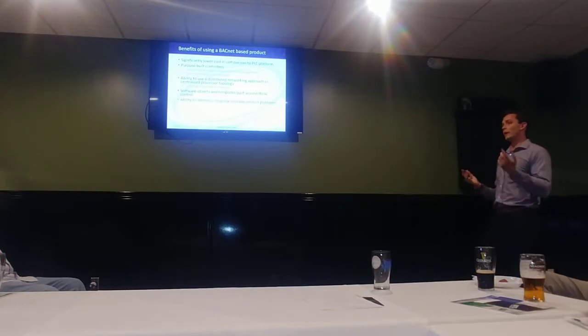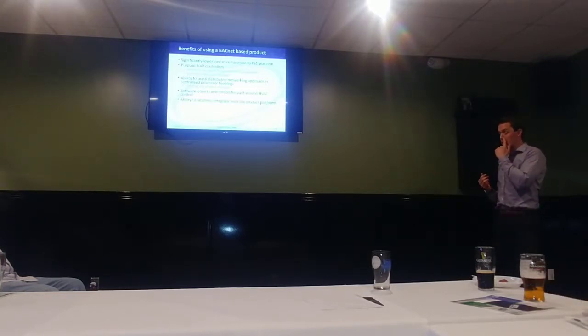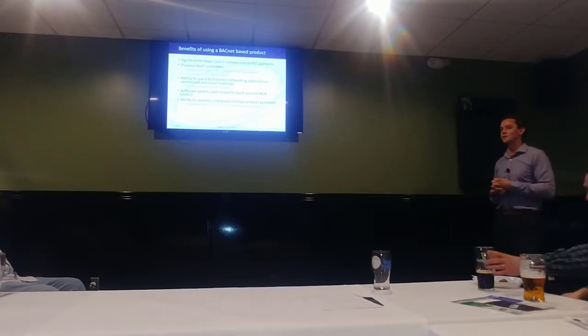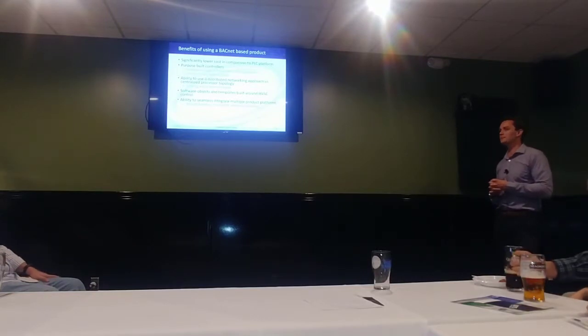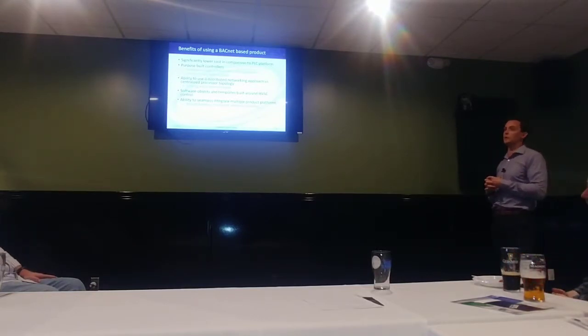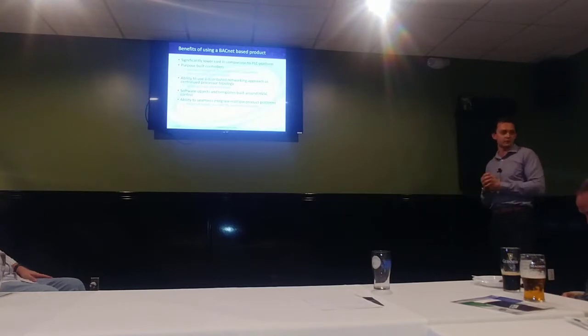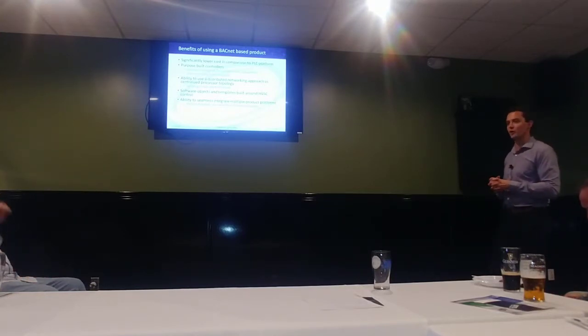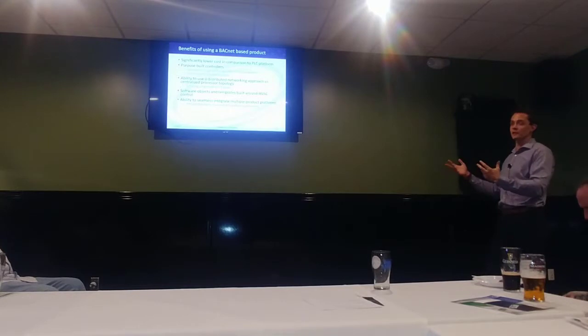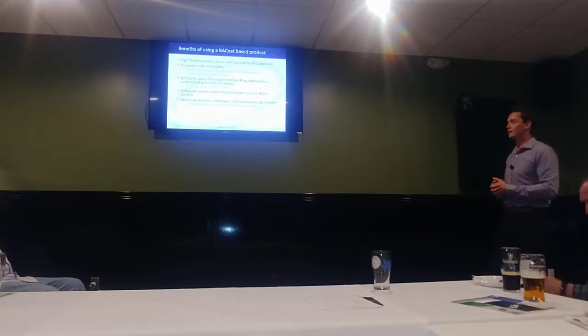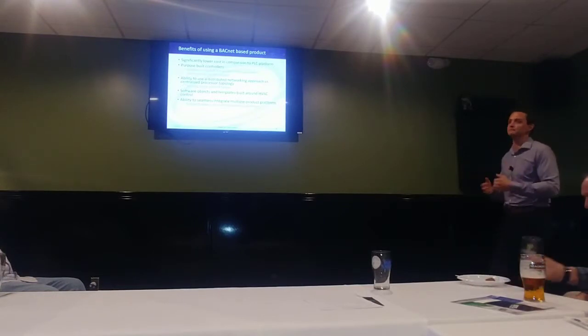So the benefit of using the BACnet product is that it is a significantly lower cost in comparison to PLCs. I don't know if people have seen the cost difference, but we saved a considerable amount of money by not using PLCs to accomplish the HVAC control. A big benefit is using the purpose-built controllers. Like we said before, I think we take it for granted that we have all these wonderful controllers that can do all these purpose-built things from an HVAC standpoint. The hardware is designed specifically for it. And in the PLC SCADA world, they don't have that.